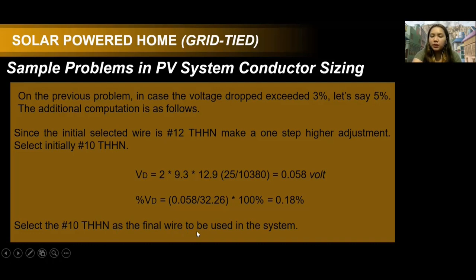Note, the K is the direct current constant. This is a constant representing the direct current resistance for a 1,000 circular mils conductor that's 1,000 feet long, at an operating temperature of 75 degrees Celsius. The direct current constant value you should use for copper is 12.9 ohms.